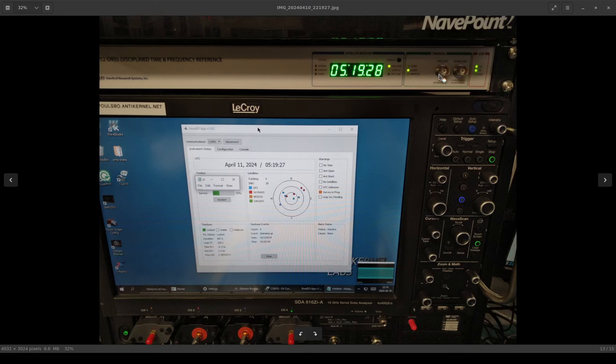And then moving to the right we have a one PPS out and a 10 megahertz out. These are the same signals that are output from the rear panel of the instrument but just additional buffered copies which are handy to have if you want to do some benchtop setup and you don't want to run cables around to the back.